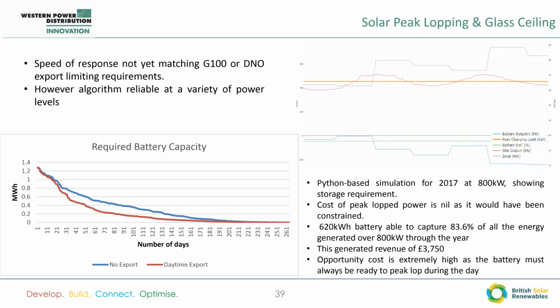The opportunity cost for this is very, very high, because the battery has to be available between sunrise and sunset every day for any time that the solar park is likely to go over 800 kilowatts. And you can't even take average irradiance figures for the next day to be able to say, well, we won't need the battery tomorrow, because there could be peaks of irradiance and then troughs, unless you therefore take the hit that the battery won't be available and you'll have to constrain what those excursions would be.